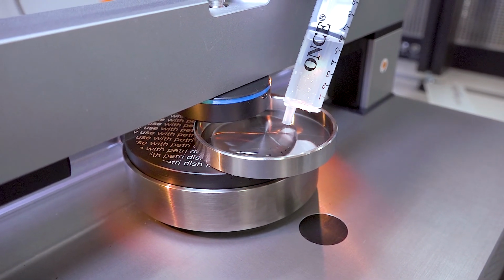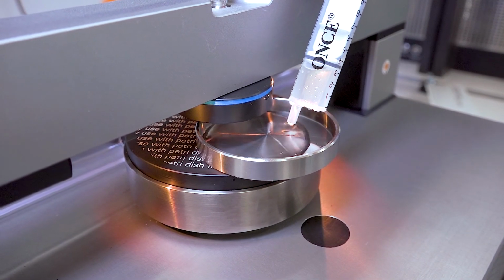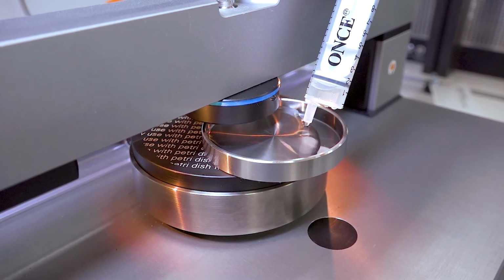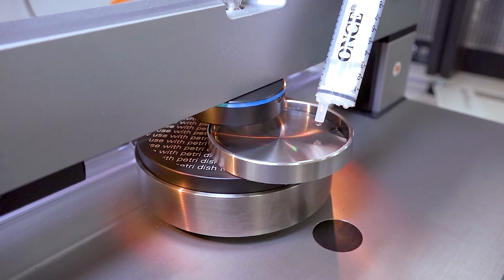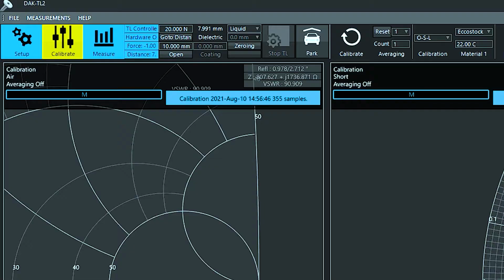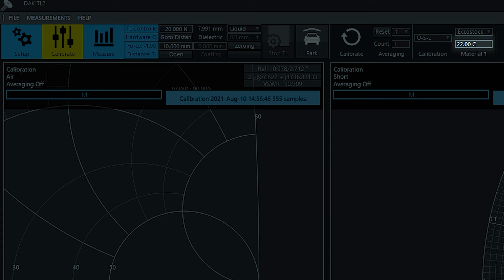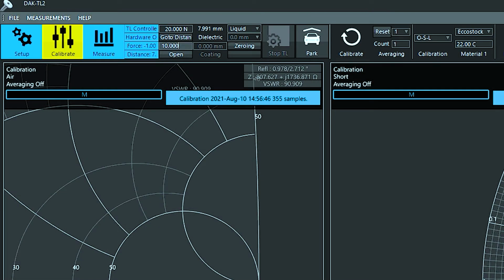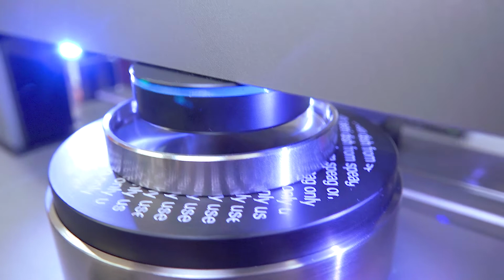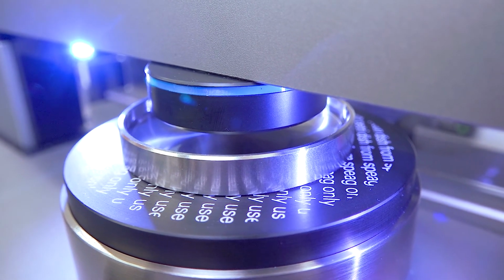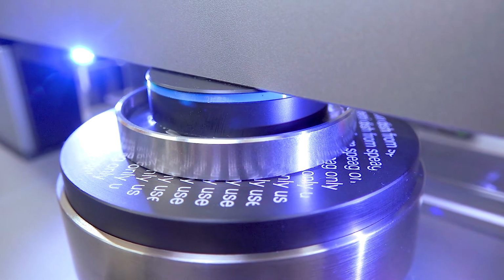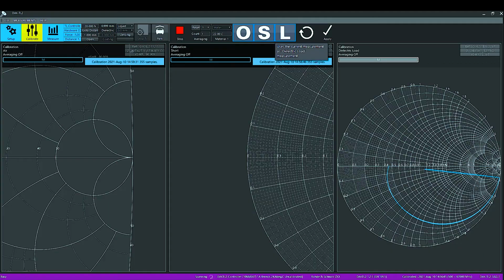For DAK-TL2 1.2e and 3.5, we recommend to use DI water, and for DAK-TL2 12, 0.1 molar saline solution as the load. I measure the liquid temperature and enter it in the software. I type in 1 mm corresponding to 10 ml of liquid in the text box and press the Go to Distance button. Depending on the liquid volume, the distance should be set in a way that the probe is immersed in the liquid. As the final step, I push the Load Calibration button followed by the Apply button.